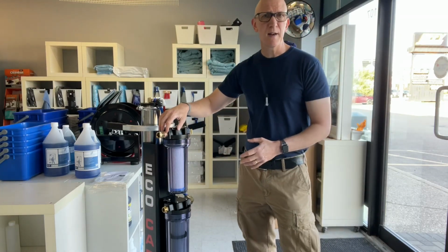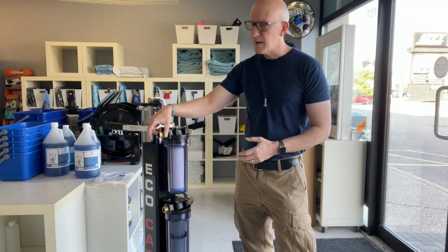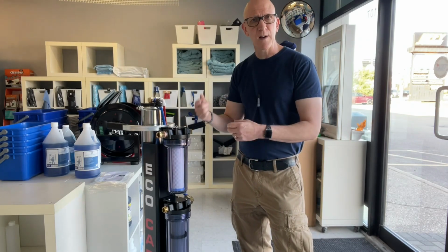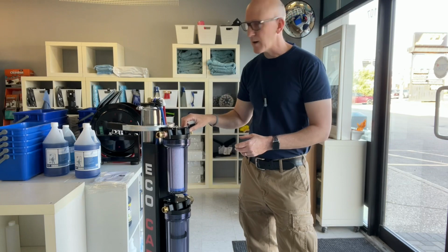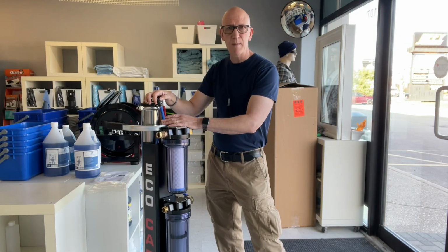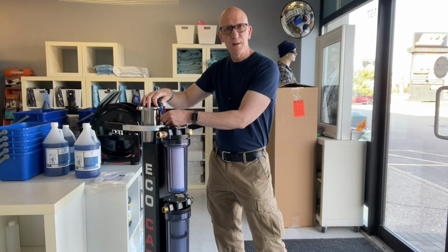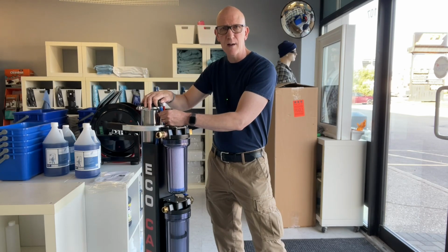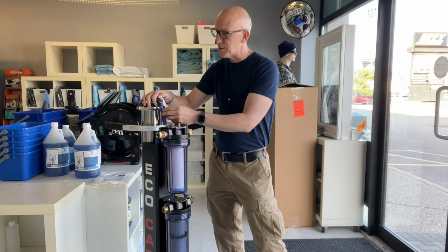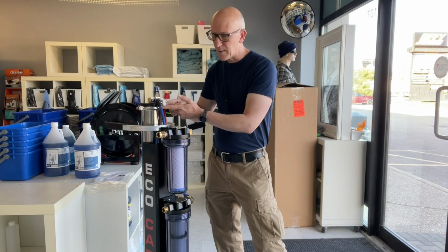For threaded fittings, if you've seen any of my other videos, it's simply a case of taking out the fitting, wrapping some fresh plumber's tape, and putting that back on. With tubing, if there's any leak there, it's usually simply because the tubing, maybe in transport, got pulled out a little bit. Usually just pushing the tubing back in will be sufficient. If you do have a broken fitting at all, certainly order up a new one.